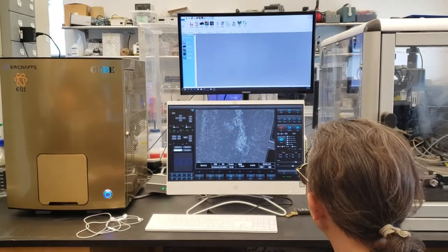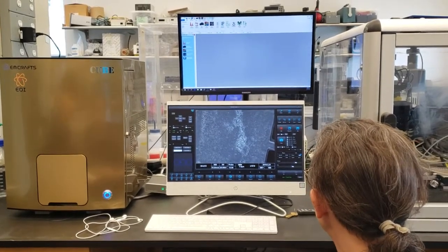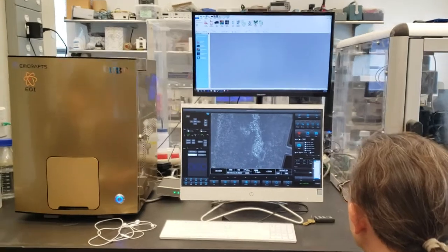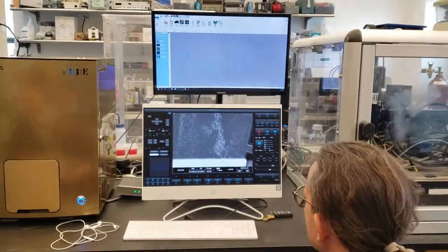So what happens is, if I have my spot size or my probe current up to 20, where the beam is really wide, you're going to see this ratio changed to 36% dead time. If I want to change that ratio, if I change this to time constant of 2, look what happened to my analysis ratio: it went from 36 to 18. I've got less dead time because I'm looking at information faster.